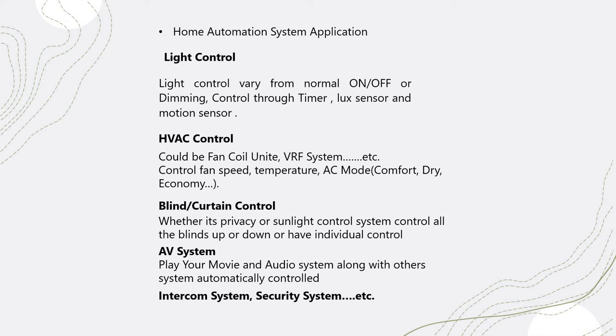For HVAC control, you can control your HVAC systems — in the Gulf region people commonly use VRV, but most commonly they use FCU-type systems. You can control the AC mode, temperature, and fan speed, and create scenarios linking with other applications. For blind and curtain control, you can control curtains whether using a 230-volt direct drive motor or dry contacts, sending commands to operate curtains fully open, fully closed, or at a set percentage such as 50% open.